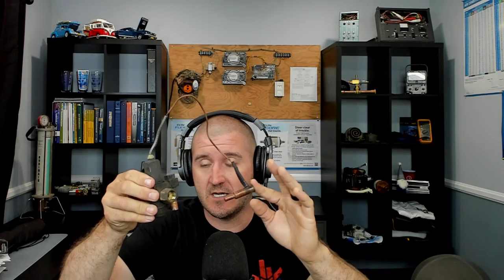It's a rendition of a temperature responsive expansion valve that Sporlan has, but this right here was custom designed for Copeland. It's meant to go on a rotolock connection on the compressor. Under really high compression ratio situations on low temp compressors, this right here helps to cool the head of the compressor, because that can be a problem.